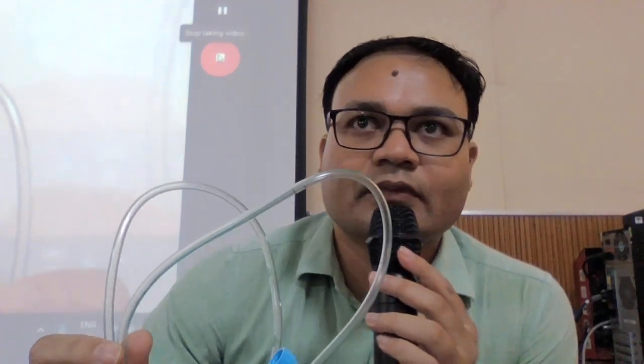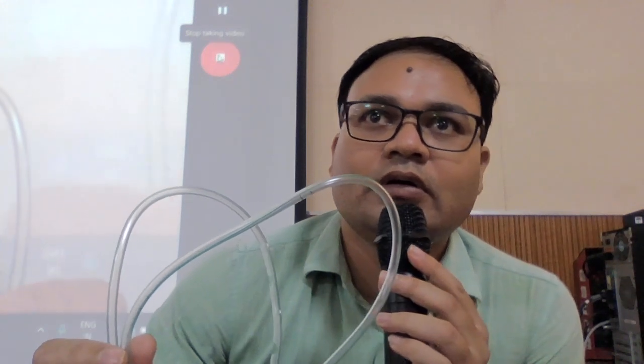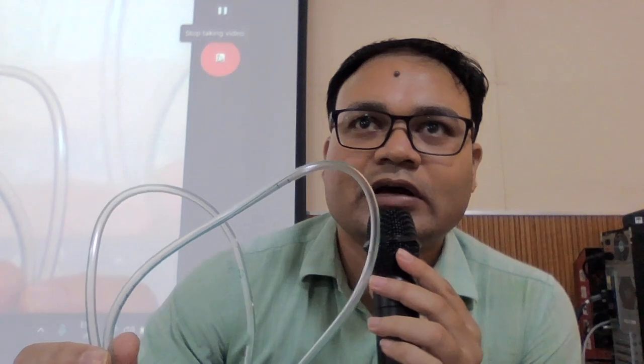Now, how do you sterilize it? Autoclaving? It's not a metal. It is made up of polyvinyl chloride, so it should not be autoclaved. It should be sterilized either by gamma irradiation or ETO, ethylene oxide. Fine. So it is sterilized by gamma irradiation or ethylene oxide, ETO sterilization.